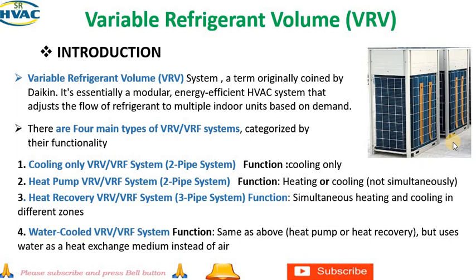First is the cooling only VRV or VRF system. Two pipe, it will provide only cooling, no heating. The second is the heat pump VRV or VRF system. This is also a two pipe system. It will either heat or cool. Simultaneously, it will not give one zone heating and one zone cooling. It will either provide heat or provide cooling in a building. The third is the heat recovery VRF system. This is the three pipe system. It will give simultaneous heating or cooling in different zones. The fourth is the water cooled VRV VRF system. The rest will remain the same, but it will use water as the heat exchange medium instead of air.